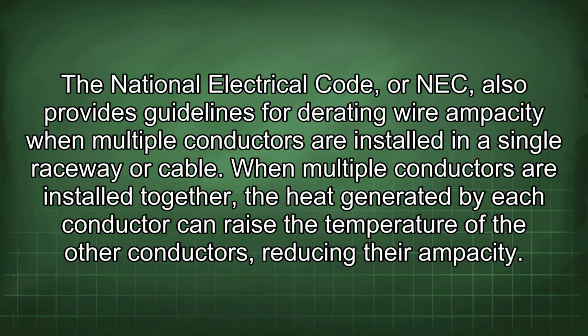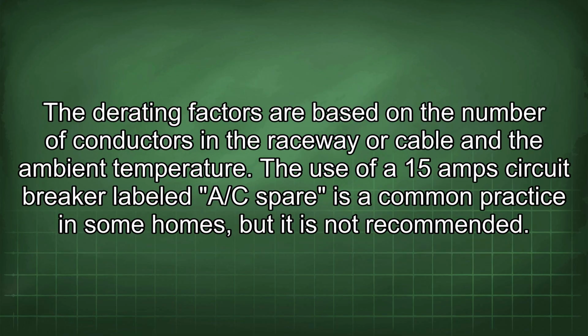The National Electrical Code, or NEC, also provides guidelines for derating wire ampacity when multiple conductors are installed in a single raceway or cable. When multiple conductors are installed together, the heat generated by each conductor can raise the temperature of the other conductors, reducing their ampacity. The derating factors are based on the number of conductors in the raceway or cable and the ambient temperature.